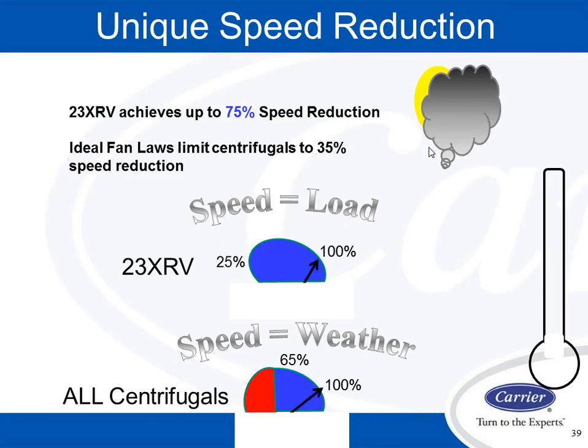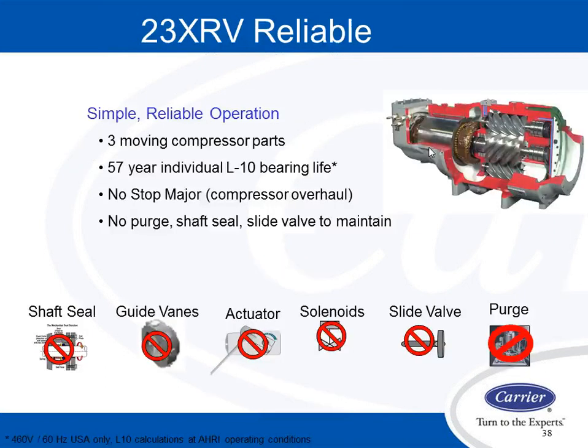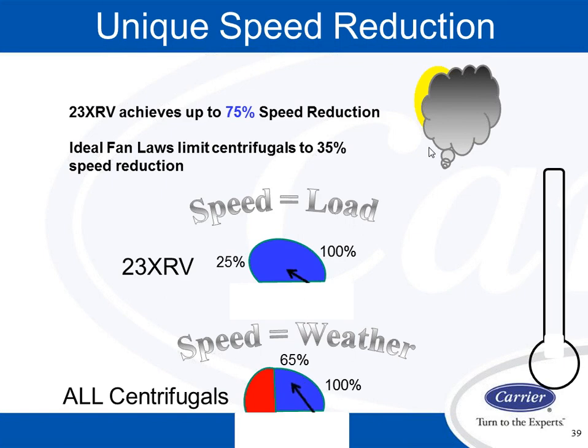We discussed earlier, and I'm going to show you again the slide where we said that the 23XRV can achieve 75% speed reduction. The ideal fan laws of a centrifugal limit it to only 35% speed reduction. Now, what a VFD does on a centrifugal is it is a lift reducing device. So it's not a part load device, it's a lift reducing device. So we could be operating here at 65% speed, at 35% speed reduction.